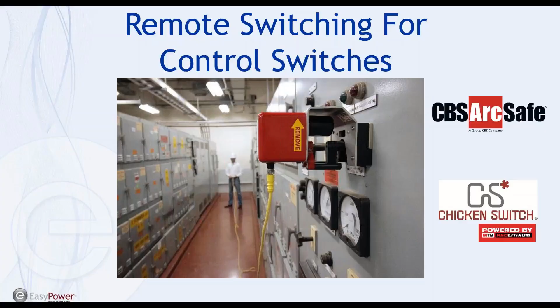We also have RSA devices from CBS ArcSafe. There are situations where remote charging of a charging handle is required. Some companies have policies that say if you're going to charge it, you need to either wear PPE or use this equipment to pull that lever, and on certain circuit breakers that is certainly the case — you could be pulling that charging spring handle and the breaker will close, since they're designed to do that. The good news is CBS ArcSafe is an expert in understanding these breakers and knowing which ones have those features in place.